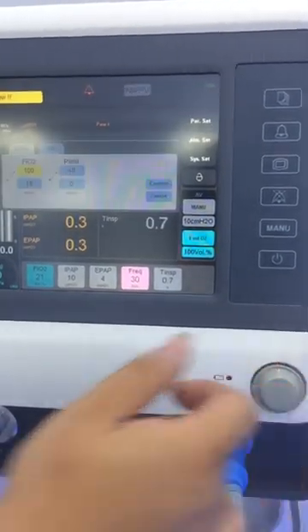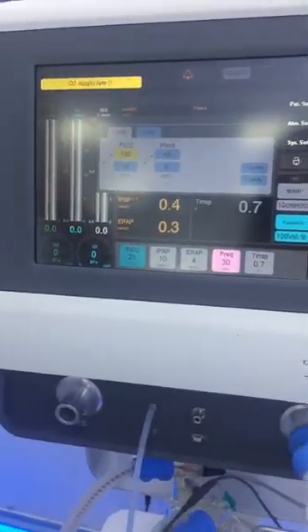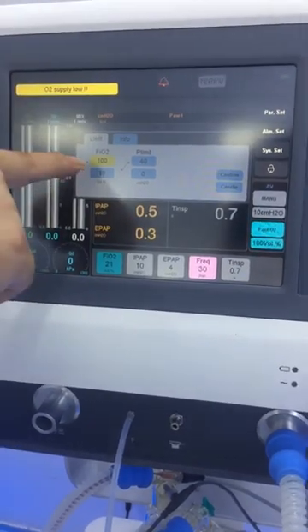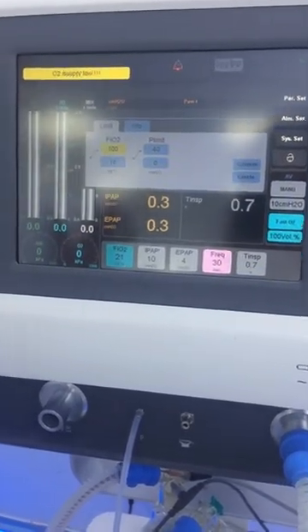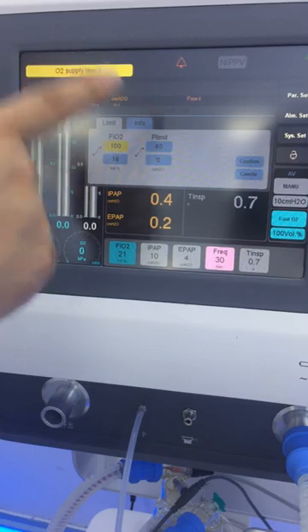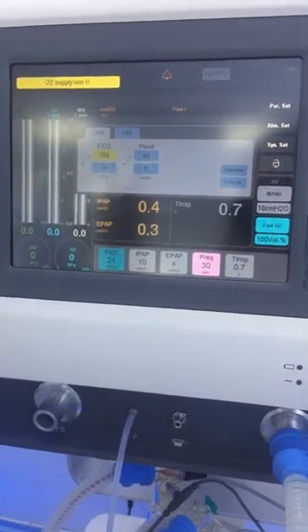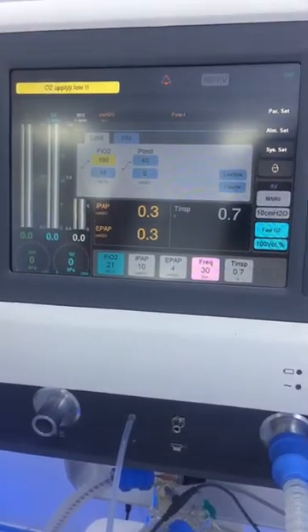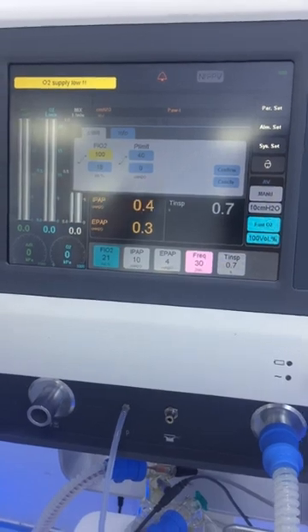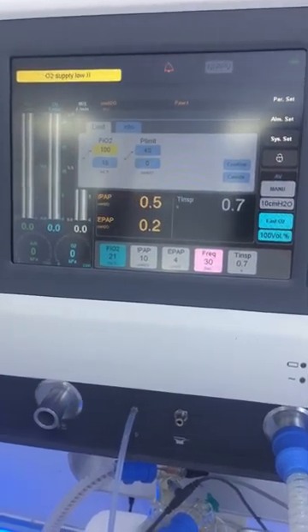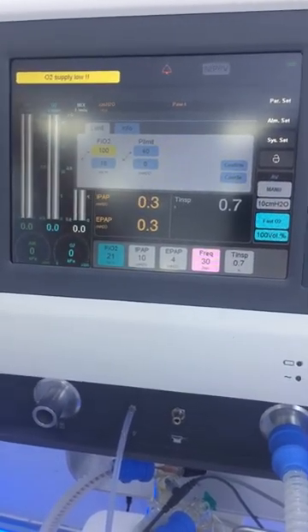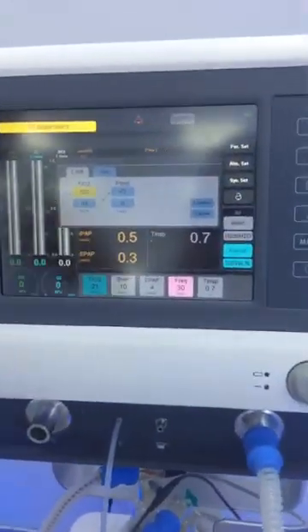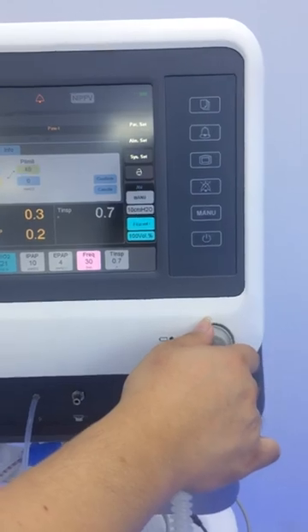And then the second one is the alarm setting. For the alarm setting, there are two columns. For the first column, you can see there's the upper limit and the lower limit for the oxygen concentration and the pressure limit. Because we know in different countries, the baby status is also different. So sometimes in the European countries or America or maybe Africa, the baby's body will be much bigger than in Asia. So sometimes the upper limit and lower limit, we need to adjust.